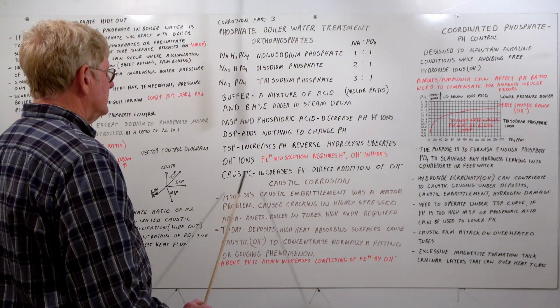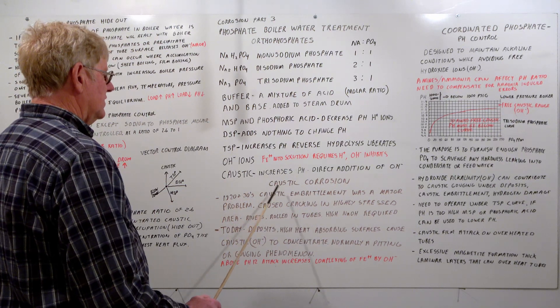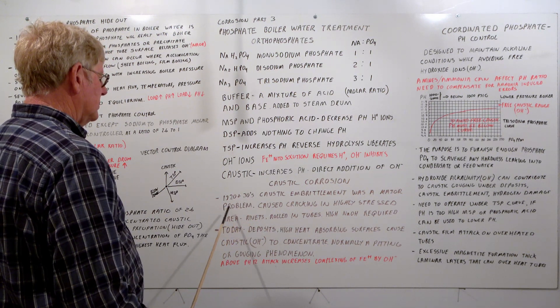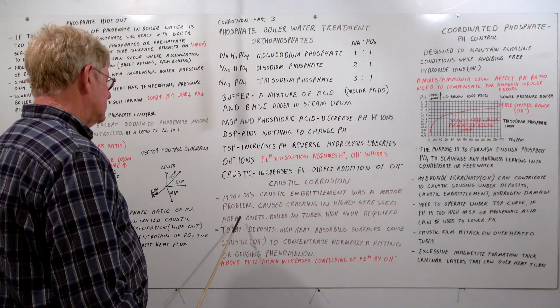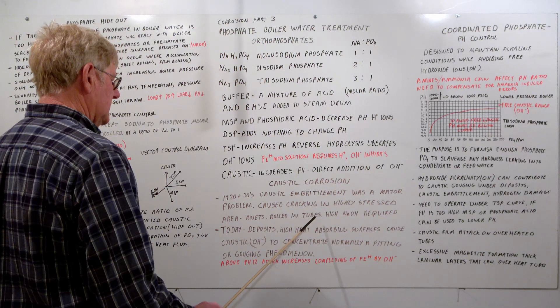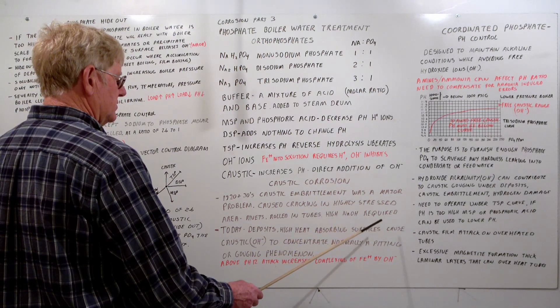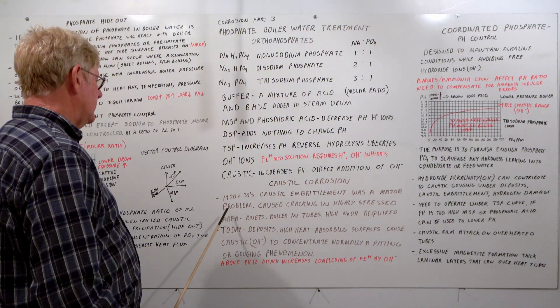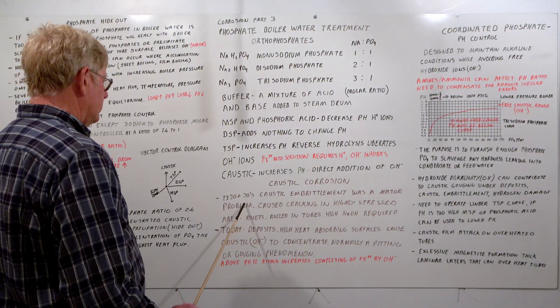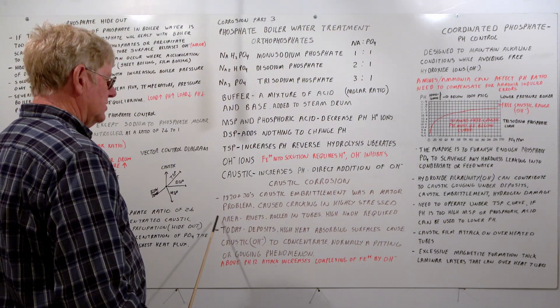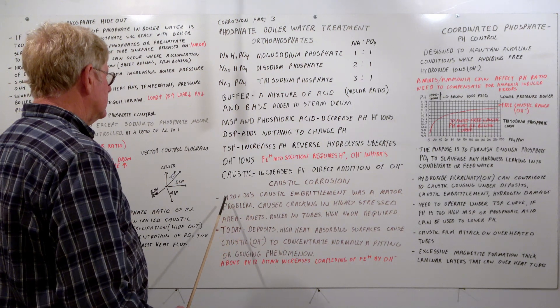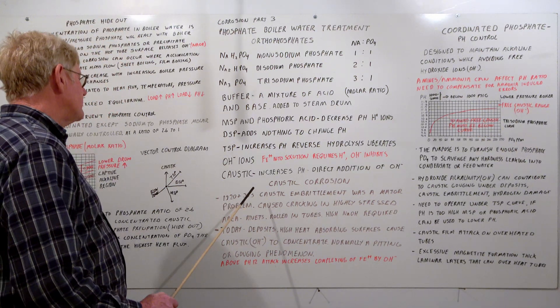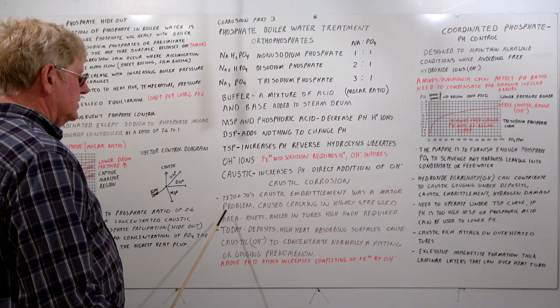Caustic increases pH through direct addition of OH. The main problem with phosphate control is caustic corrosion. In the 1920s and 30s, caustic embrittlement was a major problem — it caused cracking in highly stressed areas, particularly in riveted and rolled tube construction. High sodium hydroxide was required to form this, but even though boiler water may have had low levels, it was capable of concentrating in areas with leaks or under hot plates. One of the reasons phosphate was added to boilers is it handled calcium and magnesium hardness, making a calcium and magnesium phosphate that dropped out as a light sludge, easily blown out of the mud drums.